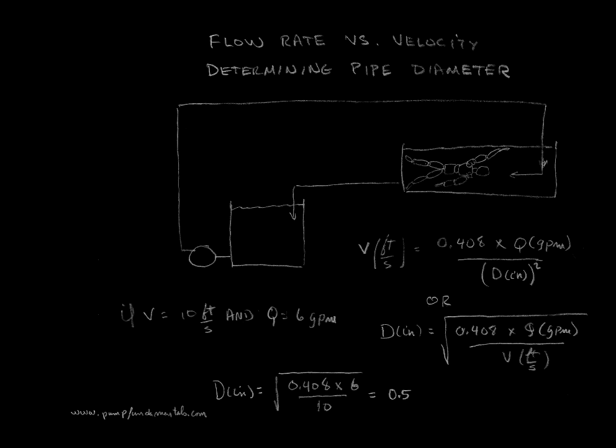Since pipe in that size is not much more expensive, whether you buy a half inch or three quarter inch, I would be tempted to use three quarter inch to lower the velocity and reduce the friction head. Remember, the goal is to achieve the flow rate of six gallons per minute and not a set velocity. The diameter we are talking about is the internal diameter. Most pipes that you can purchase at the hardware store are given in nominal pipe size, which is larger than the internal diameter and closer to the outside diameter.